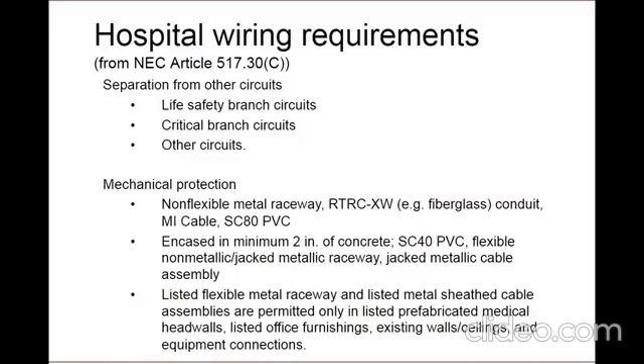If you recall in an earlier slide, the branch circuits in patient care spaces had a requirement for the raceway or cable system to be suitable as an equipment grounding conductor. This requirement precludes the use of any non-metallic raceways in patient care areas.